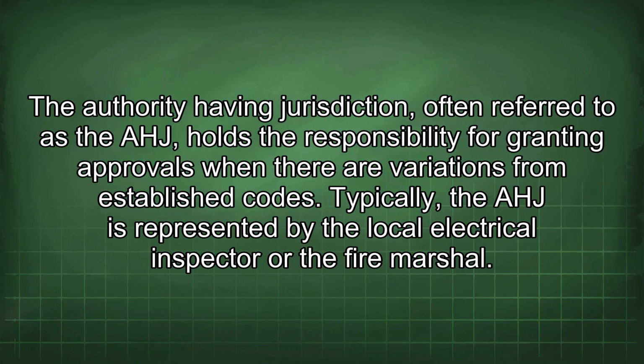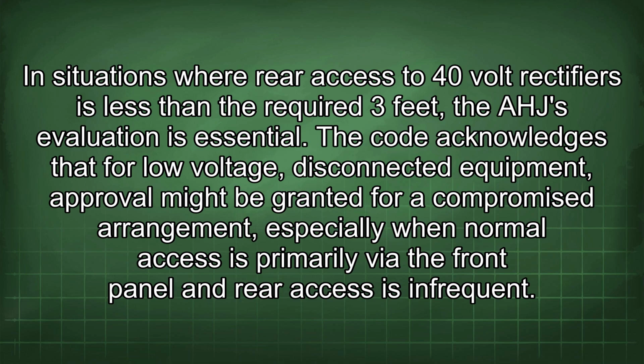The authority having jurisdiction, often referred to as the AHJ, holds the responsibility for granting approvals when there are variations from established codes. Typically, the AHJ is represented by the local electrical inspector or the fire marshal. In situations where rear access to 40-volt rectifiers is less than the required 3 feet, the AHJ evaluation is essential.